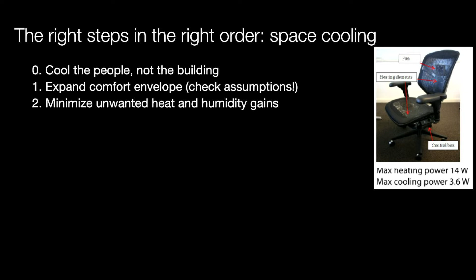Then you expand the range of conditions in which people feel comfortable. For example, good ceiling fans can expand the summer comfort range by 5 to 7 Celsius. Then you minimize unwanted heat or humidity gains within or into the space. Then you apply passive cooling, then active but non-refrigerative cooling.